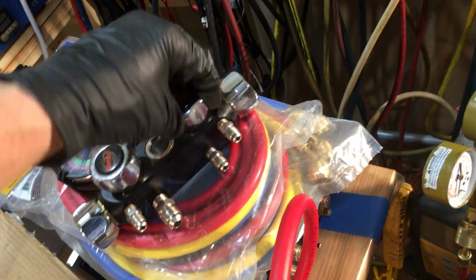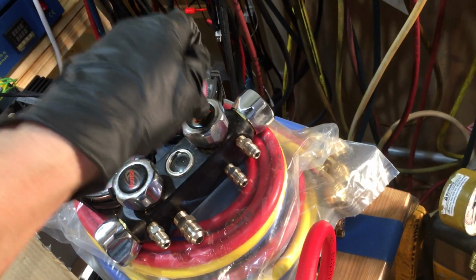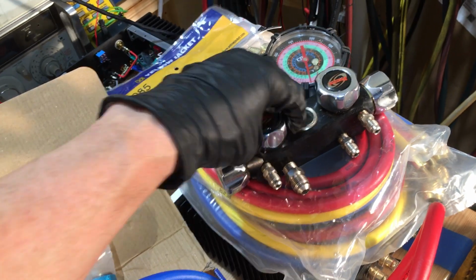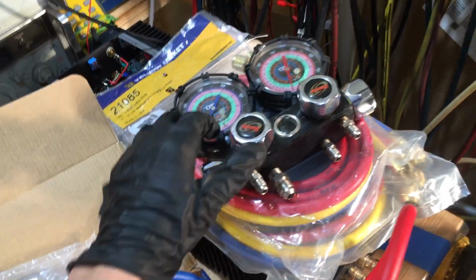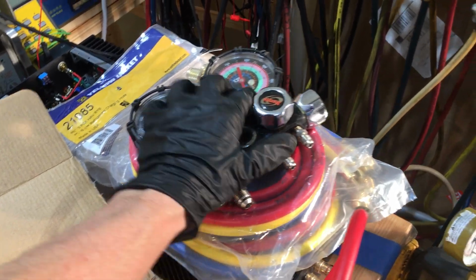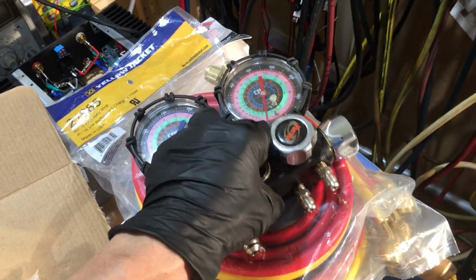They leaked at these fittings in here, vacuum leak. They could not hold high pressure at 600 psi. They leaked under deep vacuum. When I tried to go under 500 microns, they leaked. So that was a fail.